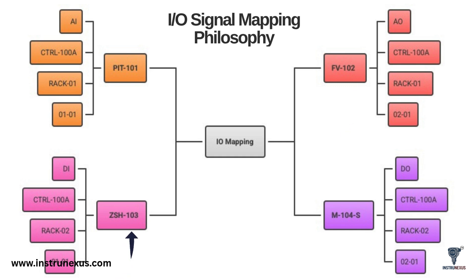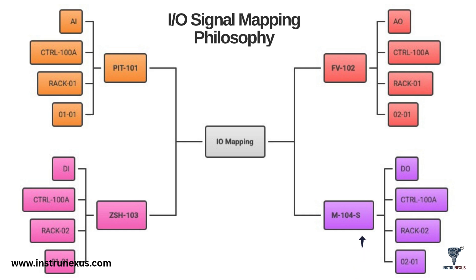Third, ZSH-103, a high level switch. This sends a simple on-off status, so it's a DI (digital input). It's wired to RACK-02, slot 01. This is how the DCS knows the level is high. Finally, M104S – the start command for a pump – is a DO (digital output). The DCS sends an ON command from RACK-02, slot 02, to tell the motor control centre to start the pump. Every single field device is systematically mapped to a specific address, connecting the physical plant to the digital control system.